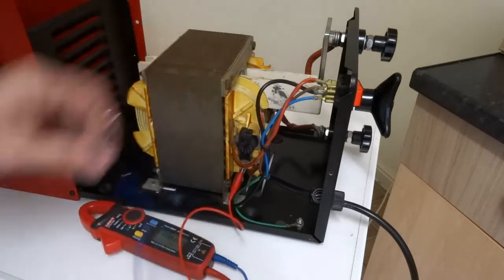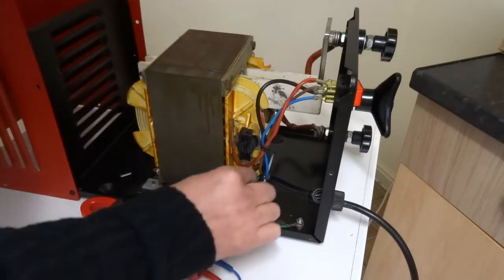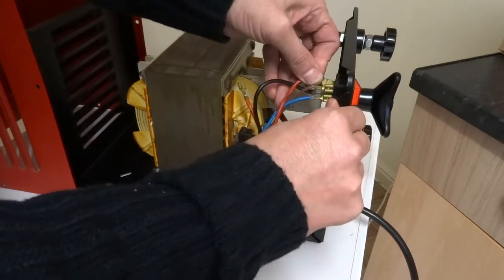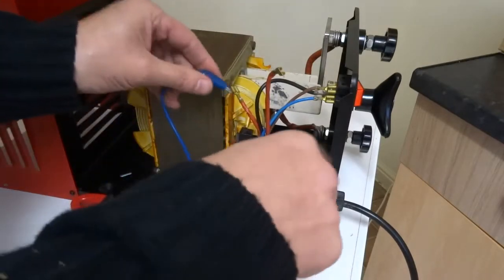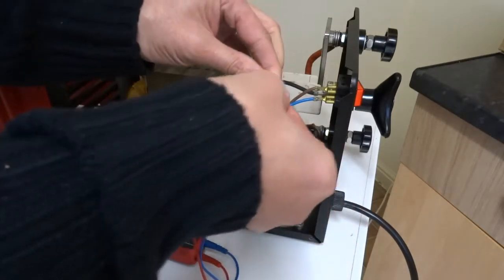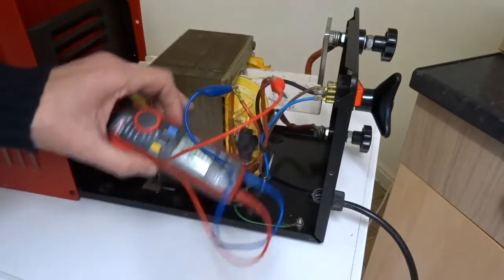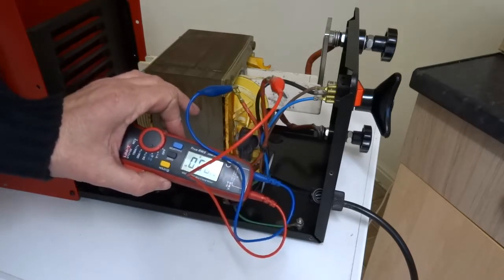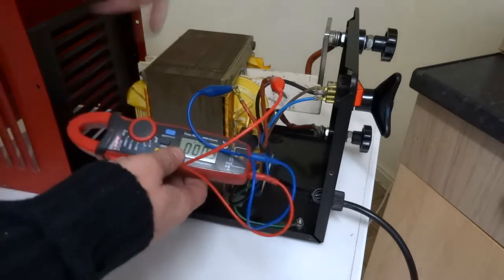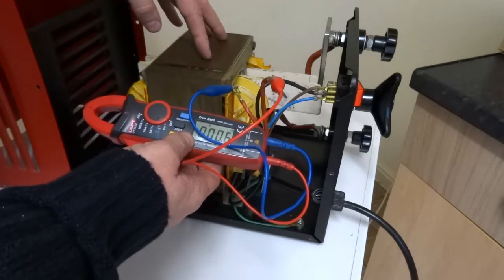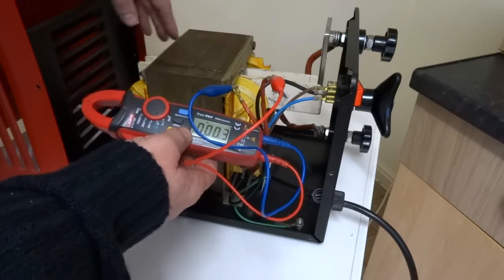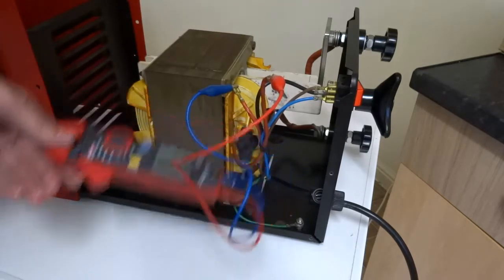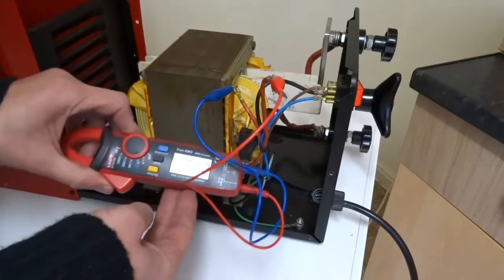It's buzzing, so put the black cable back on. Now I'm going to test the primary windings of this transformer, so I want to test between the two. As you can hear the buzzer beeping, it's got a very low ohm reading. That is basically a short circuit really, but because of the way these transformers work, there's loads of magnetism and reactance and reluctance and all sorts going on that stops the inrush currents from tripping the circuit breaker. So basically that's a good reading, really low ohms.